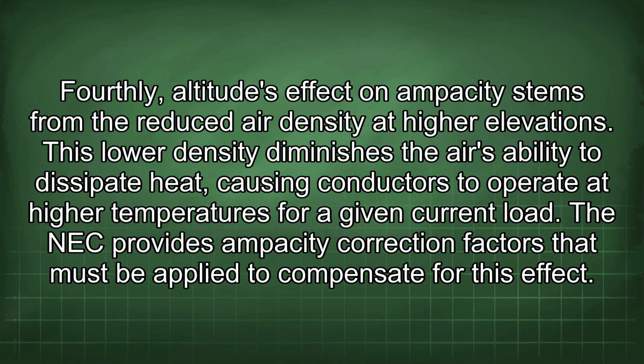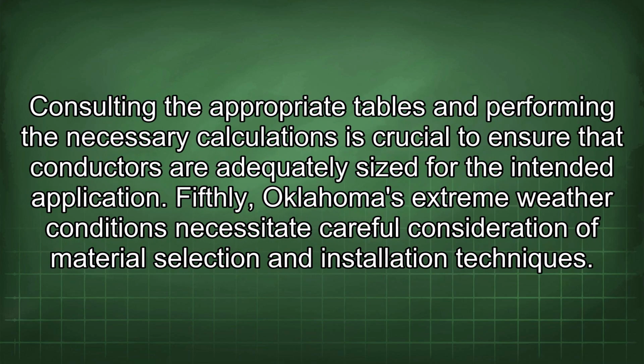Fourthly, altitude's effect on ampacity stems from the reduced air density at higher elevations. This lower density diminishes the air's ability to dissipate heat, causing conductors to operate at higher temperatures for a given current load. The NEC provides ampacity correction factors that must be applied to compensate for this effect. Consulting the appropriate tables and performing the necessary calculations is crucial to ensure that conductors are adequately sized for the intended application.